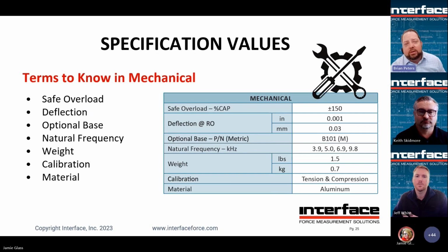On the mechanical side, so the mechanical section is going to cover safe overload, how much force above capacity can it tolerate without permanent damage, and the deflection, so that's going to be the specification of how much the load cell will move. There'll be a live end and a dead end, but how much total deflection, again, at the rated output or capacity if it's a full-scale cal. Most load cells are going to be very, very small deflection. You can see 0.001 inch in this case. Stiffer is generally better, but some lower capacity, some minis that we offer due to the design, to get desired output, etc., you may have more deflection, so it's something to keep in mind depending on what your test requirements are.